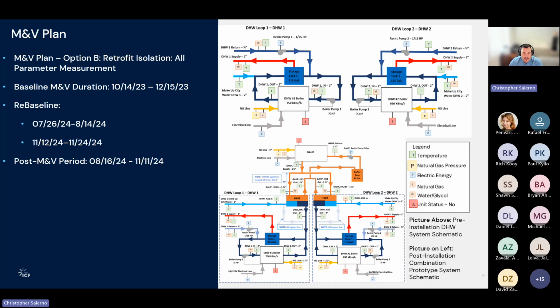That's one of the key things to take into consideration when considering this as an application: does it make sense to retrofit it? These space limitations would make it very difficult and costly. This system is about 55 feet away, using insulated underground piping. Essentially, this gas-fired absorption heat pump is supplying supplemental heat to the cold water going to both systems. That was the key objective of this diagram.